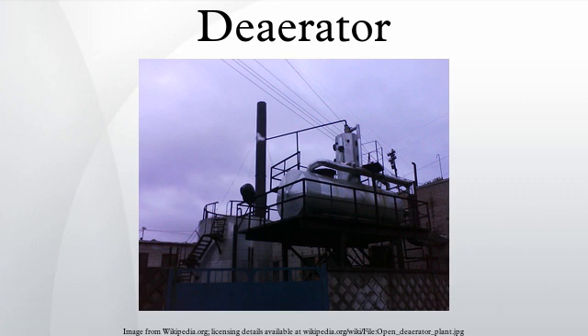Tray type deaerator: The typical horizontal tray type deaerator has a vertical domed deaeration section mounted above a horizontal boiler feed water storage vessel. Boiler feed water enters the vertical deaeration section above the perforated trays and flows downward through the perforations. Low pressure deaeration steam enters below the perforated trays and flows upward through the perforations. Some designs use various types of packed bed, rather than perforated trays, to provide good contact and mixing between the steam and the boiler feed water.